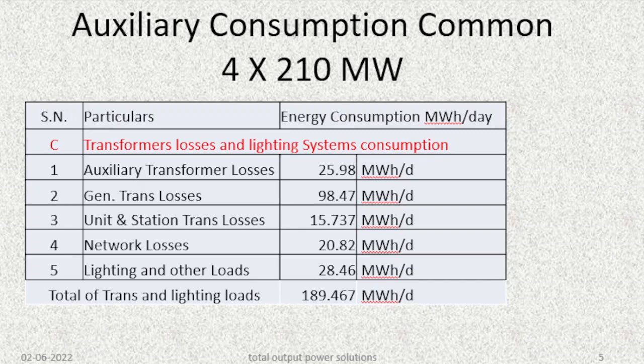There are also HT to LT conversion transformers. The auxiliary consumption for common systems of 4 x 210 MW includes auxiliary transformer losses, generator transformer, unit and station transformers, network losses, and other loads such as lighting. The total of the transformers and lighting loads was measured at around 189.467 MWh per day.